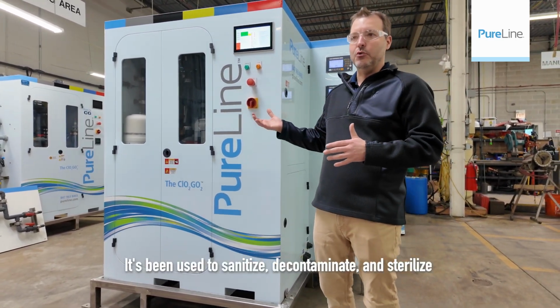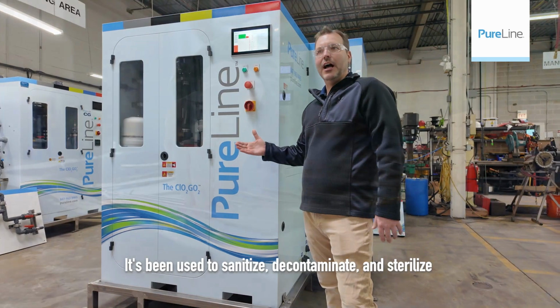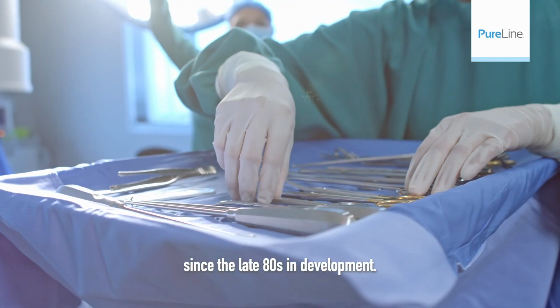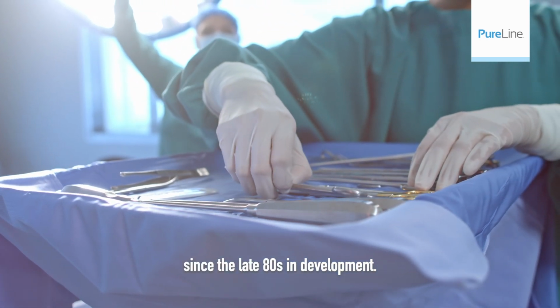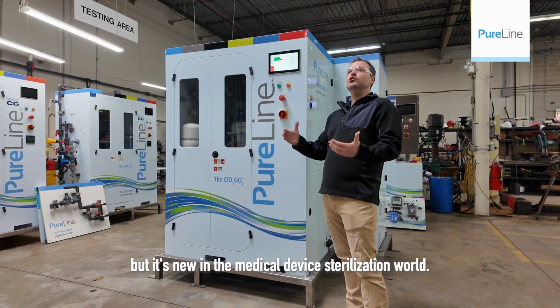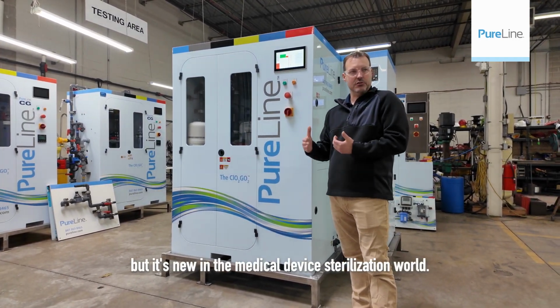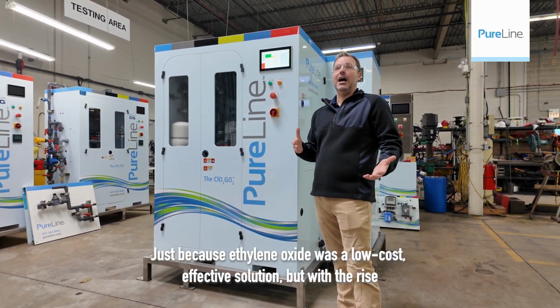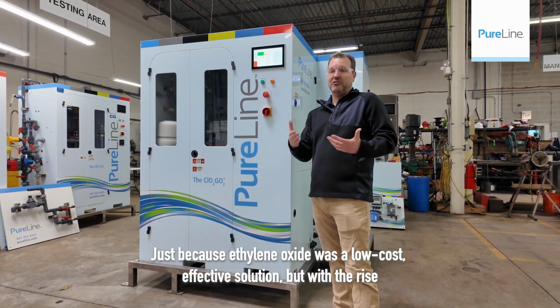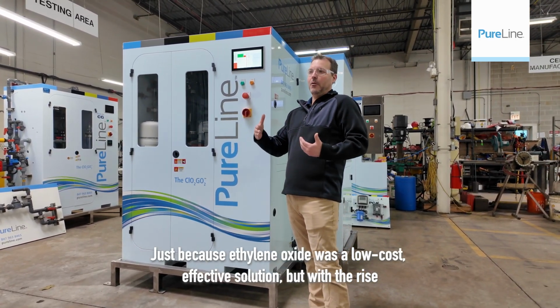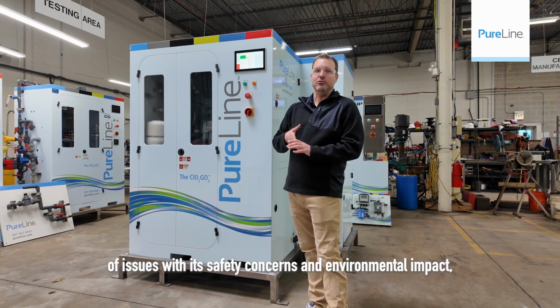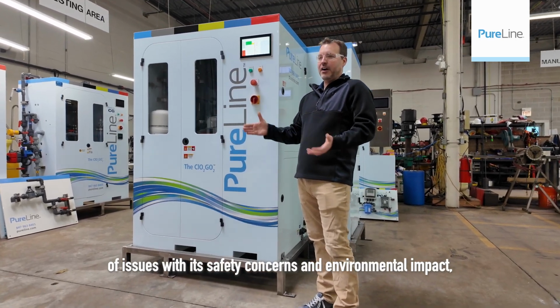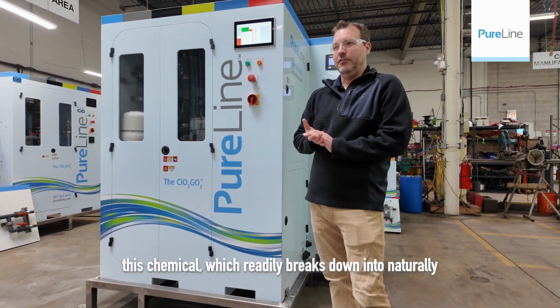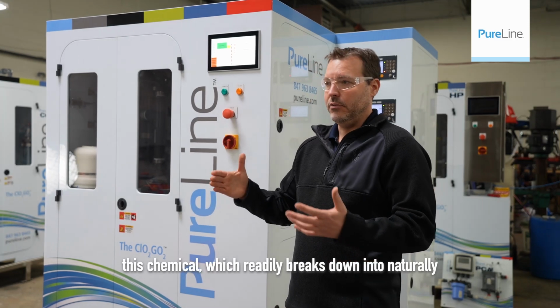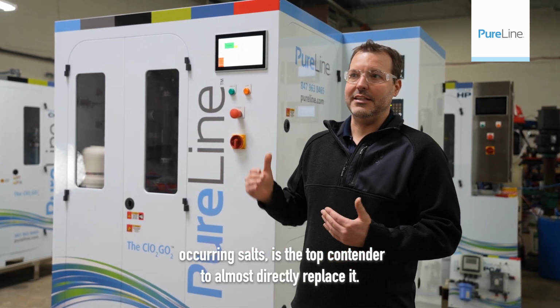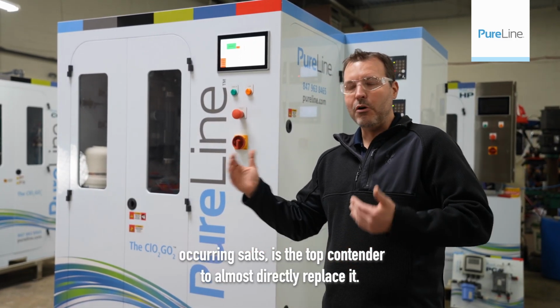It's been used to sanitize, decontaminate, and sterilize since the late 80s in development. So it's not new in that regard, but it's new in the medical device sterilization world, just because ethylene oxide was a low-cost, effective solution. But with the rise of issues with its safety concerns and environmental impact, this chemical, which readily breaks down into naturally occurring salts, is the top contender to almost directly replace it.